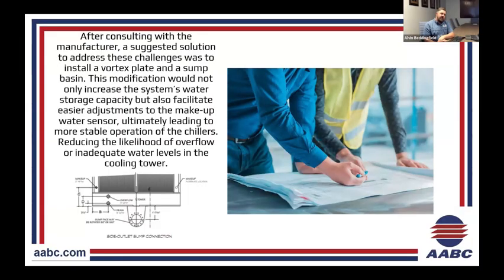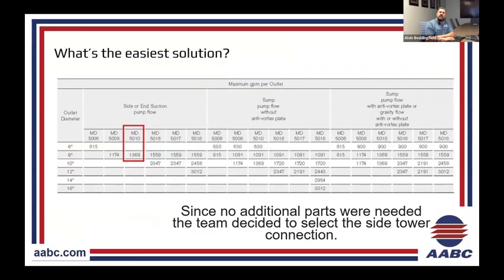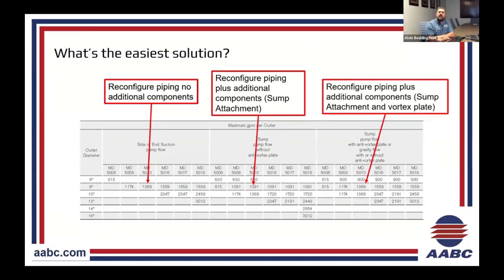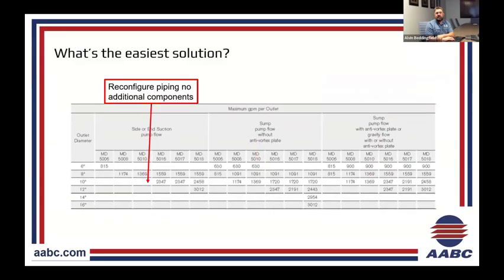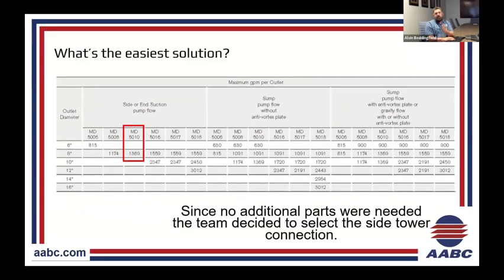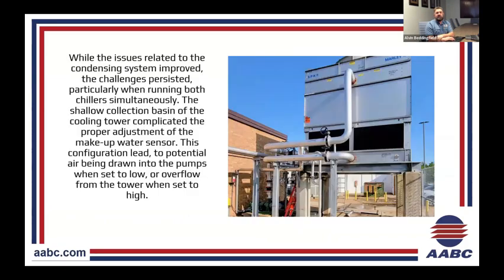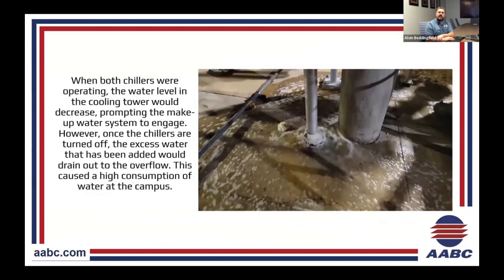So sadly enough, now we're going to try to redo this. So we'll go back to this chart, right? Now we're on sump flow. Now that we've configured the tower, we've got to reconfigure the tower and change all the piping again, which means we've got to change all the piping again at another school. And it was just around and around trying to solve these issues. And well, we went with the easiest solution. Well, easy is not always the best option.